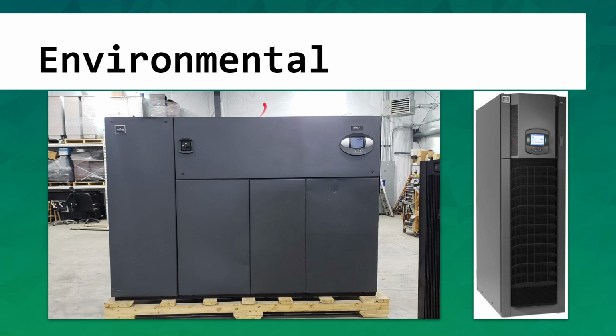What they do is suck air from the top and blow air straight down, and these work on an elevated surface. The data centers I've been in are typically elevated about 18 inches off the ground with a raised floor. Certain floor tiles have perforations, lots of holes in them, and because of the pressure of all the air going straight down, it pushes air up through those perforated tiles, which are organized right in front of the racks of servers. So the cold air shoots up and is sucked through the server. The hot air is blown out the back of the rack, collected at the top of the air conditioner, and recycled. It's the cycle, it's the circle of life.